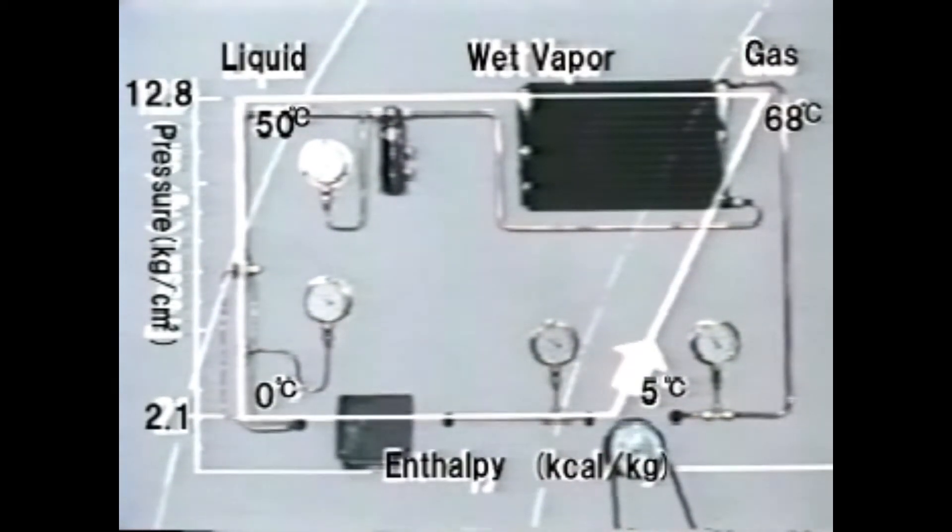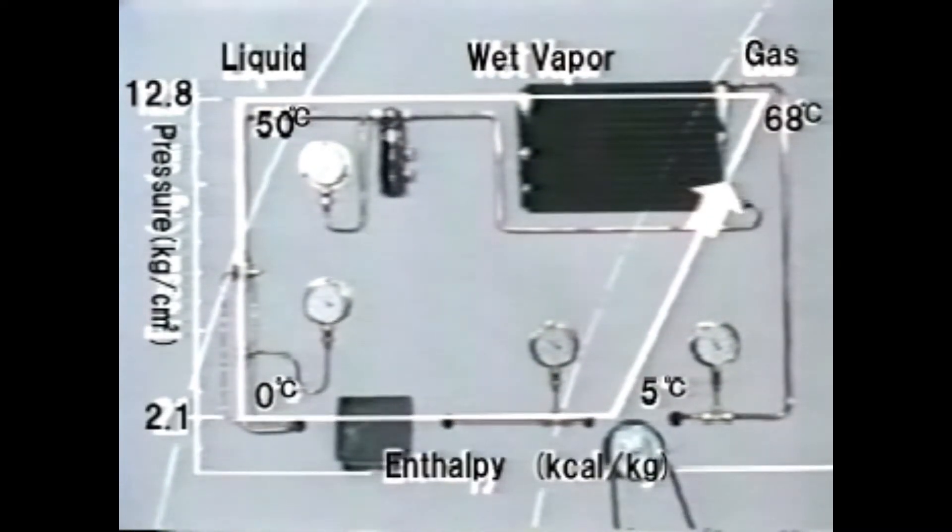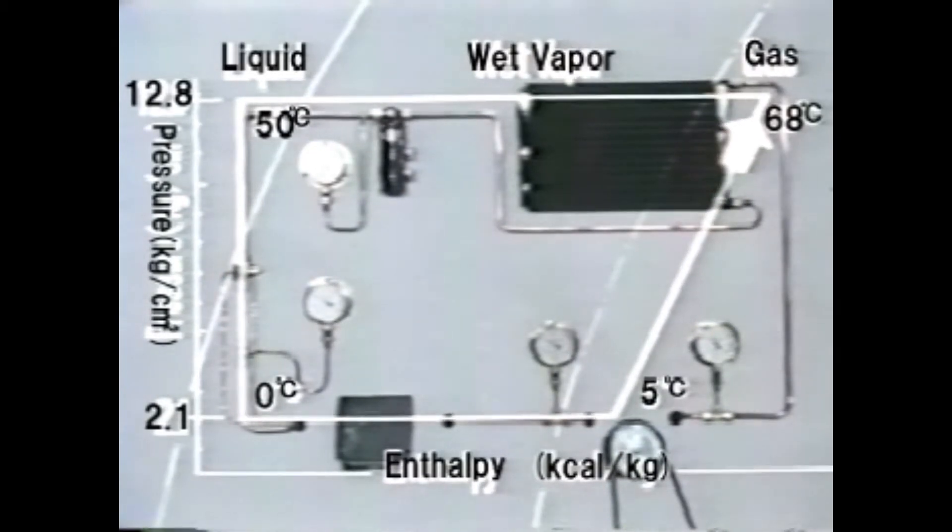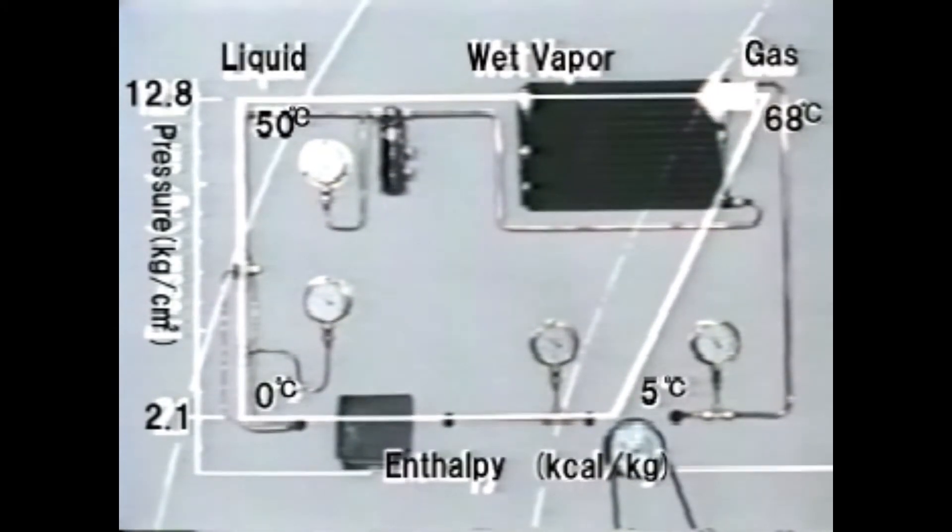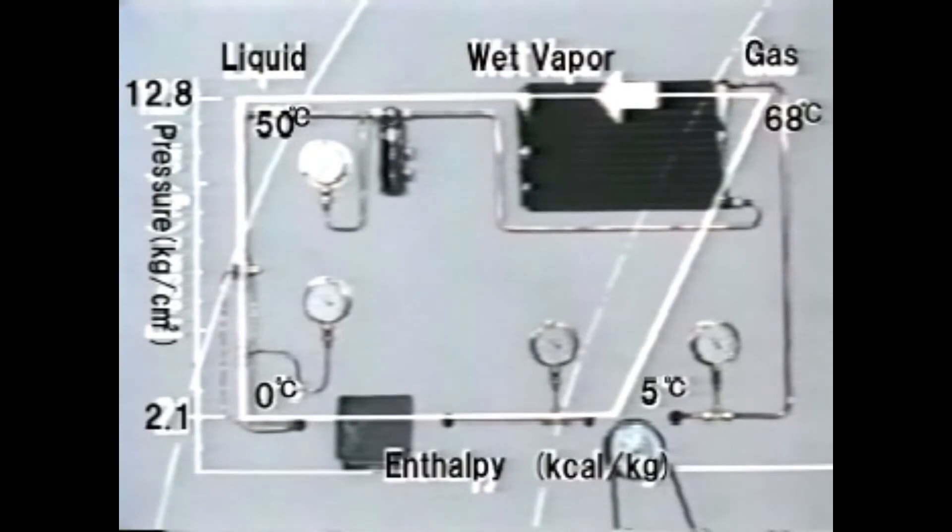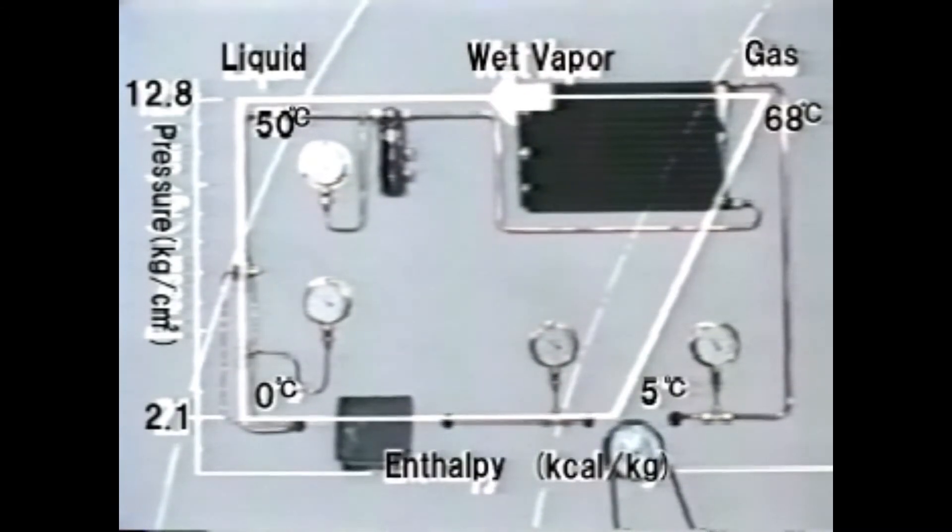And compressed in the compressor, it turns gaseous form with its pressure increased to 12.8 kilograms per square centimeter and its temperature at 68 degrees centigrade. In the condenser it is condensed under the same pressure into a liquid at 50 degrees centigrade, which is transmitted to the expansion valve.